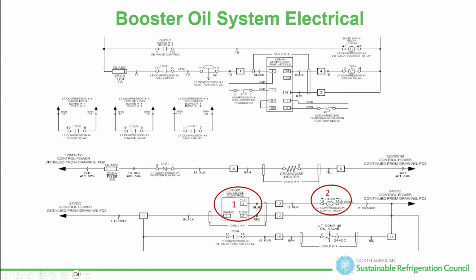I have to read the language. And so that's going to simply close this normally open set of contacts. This is a dry closure. There's no voltage, as you can see here. It simply goes to a digital input board on my controller. So all I've done so far is tell the controller which one. I don't care, RDM, Copeland, Danfoss, Microthermo comrades, right? It doesn't matter. It's a digital closure. So then I just told the controller, dude, I need oil.